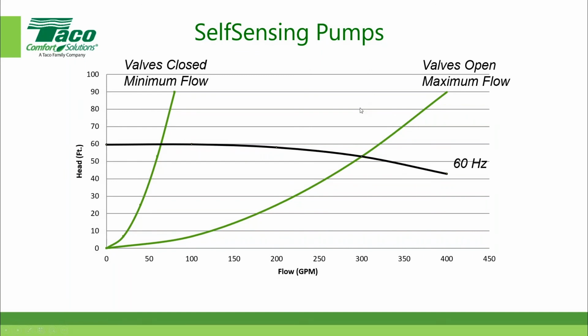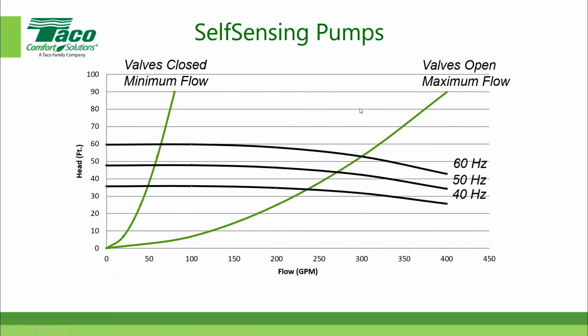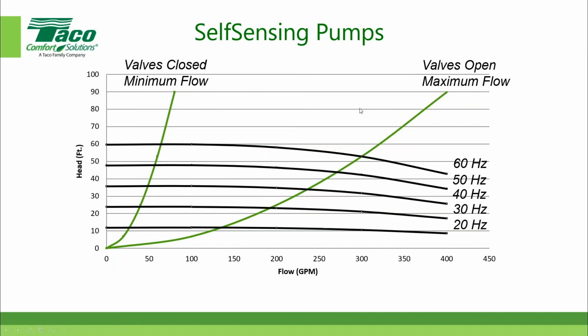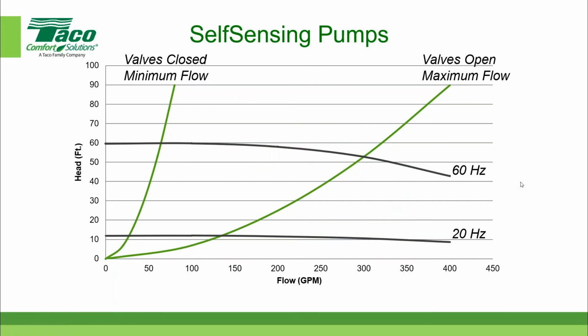So instead of running constant 60 hertz, we're going to actually change the speed of the pump from a maximum of 60 hertz to a minimum of 20 hertz. And what we're going to do is go from this maximum operating point here, 60 hertz with all the valves open, down here to 20 hertz with all the valves closed with the exception of the three-way valve. And then we're going to connect those lines with a smooth curve, and we're going to call that a control curve. So I'm going to erase that gross line that I drew and have the control curve plotted out for you.